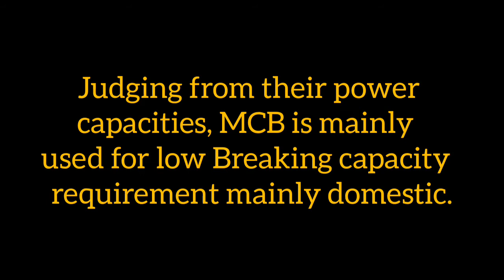First of all, there is a difference in what they stand for, where MCB stands for miniature circuit breaker, whereas MCCB stands for molded case circuit breaker. MCB rated current is not more than 125 ampere, whereas MCCB rated current is up to 1600 ampere. The interrupting current rating of MCB is under 10K ampere, and the interrupting current rating of MCCB ranges from 10K ampere to 85K ampere. Talking about power capacities, MCB is mainly used for low breaking capacity requirements, mainly for domestic purposes, whereas MCCB is used for both low and high breaking capacity requirements, mainly in industrial purposes.